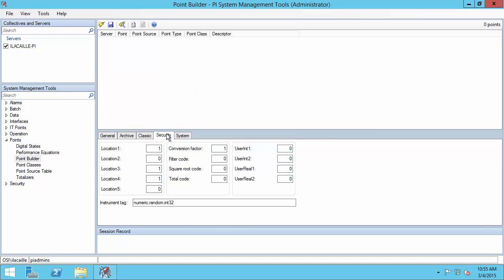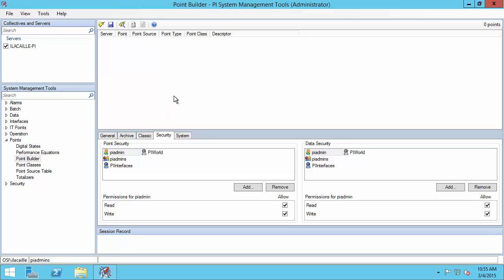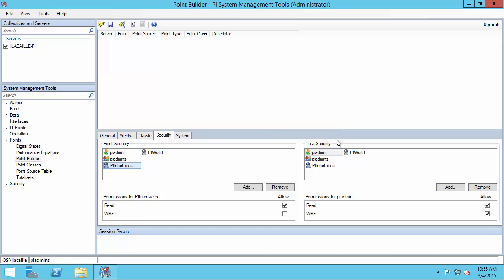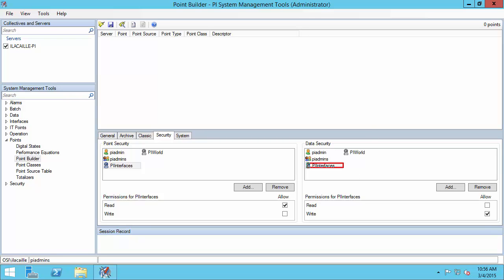Now I can go to the security tab. Here I choose for point security who has access to see my PI point on the PI Data Archive, and for data security who has access to the data in the PI point. I need to make sure my PI Interface's identity has read access to the PI point so it can find it when it scans the PI Data Archive — it does, so we're good. For data security, I need to make sure the PI Interface's identity has write access so it will be able to write data, so I'm going to change it from read to write. Note that once you configure buffering, it will be your PI Buffer writing to the data in the PI point, so you'll need to change this from the PI Interface identity to the PI Buffer identity.